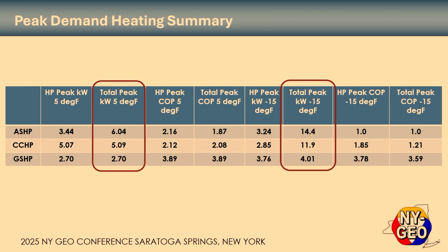So, you know, I think the interesting thing is there's no doubt that the cold climate air source heat pump has made significant progress with the technology advancements that Bob referenced. This is trying to get a level set of where we are after we implement those improvements. When we talk about peak load impact to utilities, 1,000 homes on GEO at sub-zero temperature will save 10 megawatts of peak load impact for the utility, which is not negligible. That's somewhere between a third or a sixth of an incremental IC gas turbine that costs them $2,000 a kW for the initial cost to install it. So it's $20 million for every 10 megawatts they have to put in.